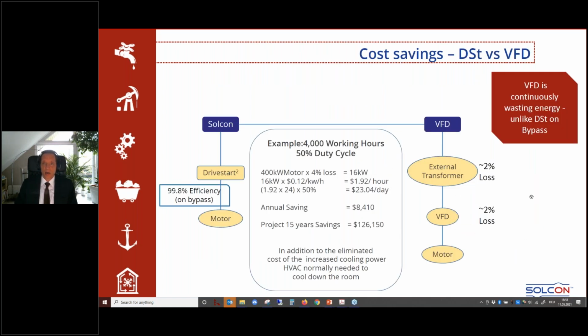One word about cost saving, drive start versus VFD. Normally, it is normal that with the VFD you save energy, and this is very much true when it's coming to applications that need variable frequency. Then surely you will save energy with operating a pump at variable frequency, that's for sure. But in fixed speed applications, some customers want to have a full power VFD continuously running, and then it starts that you can save money.